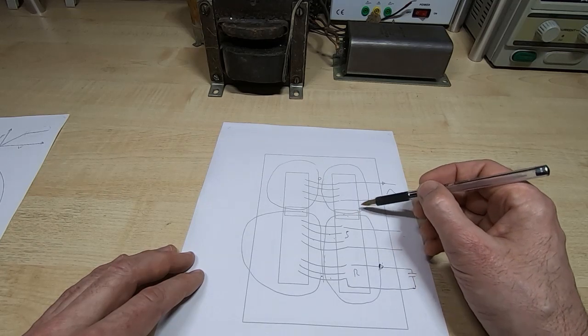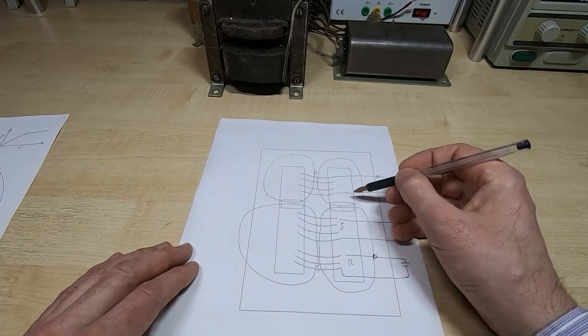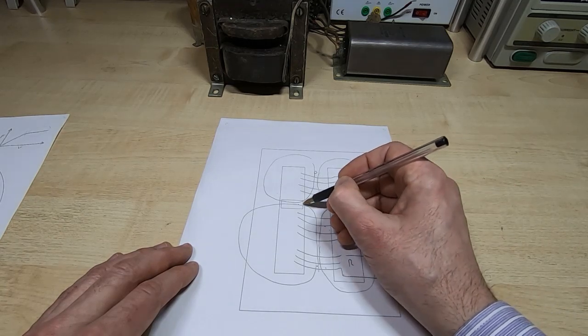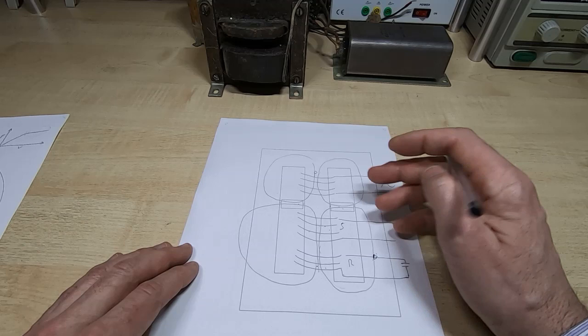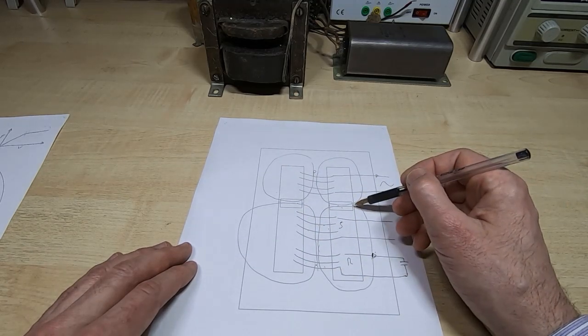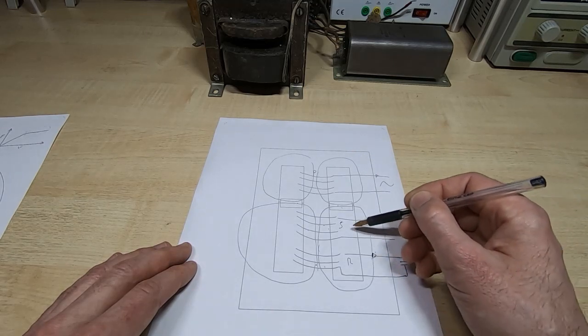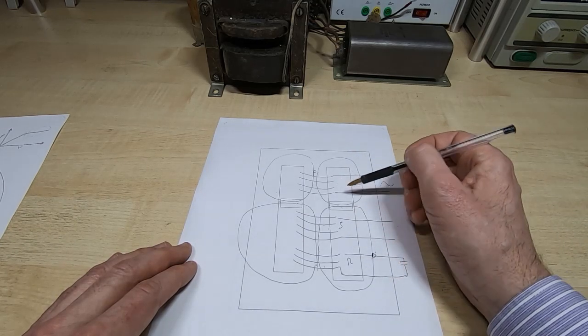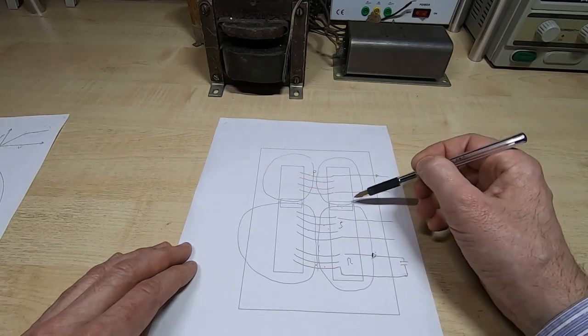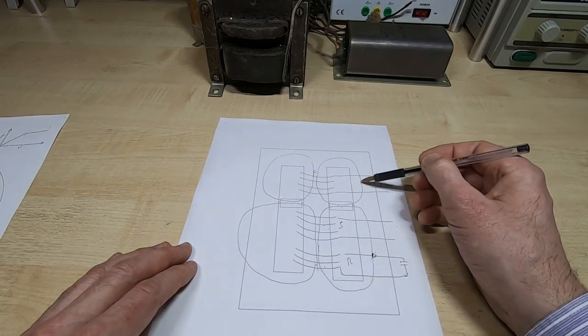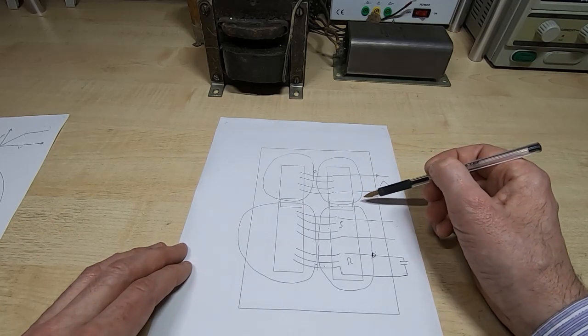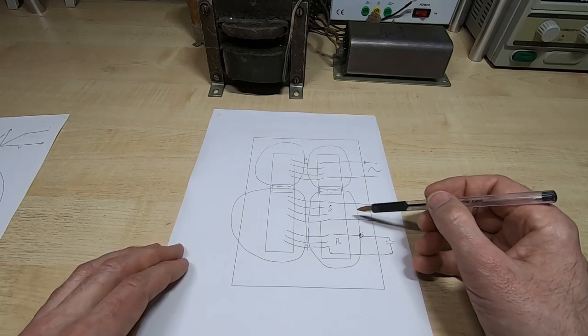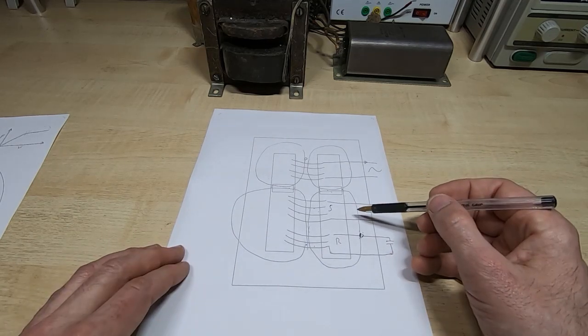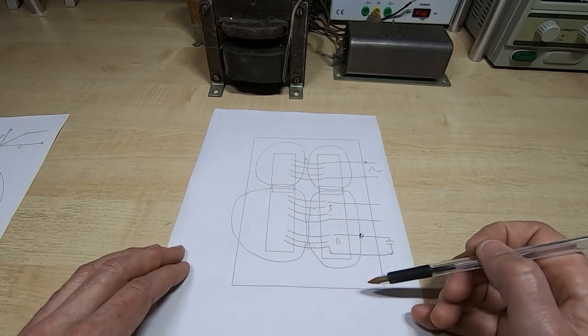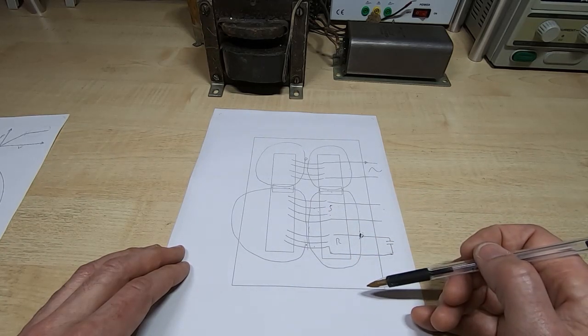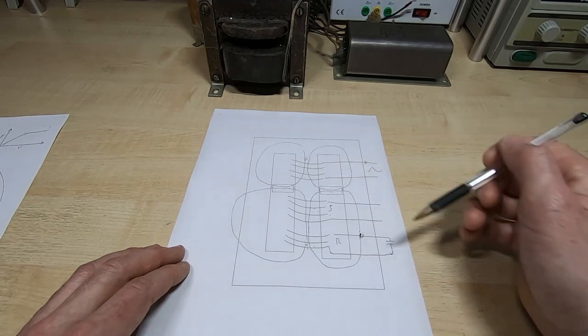Now, you can't separate them entirely, of course, because they do need to be coupled together, and that's why you have these air gaps. The size of the air gaps, the size of the shunt, and the design of the core are such that the amount of coupling between the secondary windings and the primary winding, and the resultant interaction between the two parts of the transformer, are designed to make sure the transformer can operate under its nominal load configuration or design, such that the secondary is operating in the flat saturated section and the primary is in the linear section.